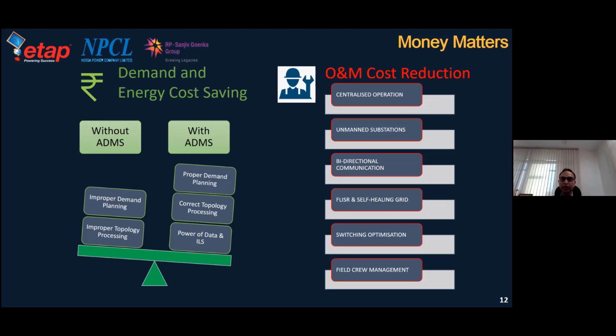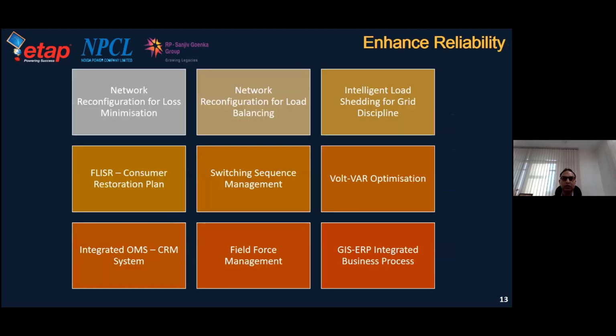In the fault localization, isolation, supply restoration scheme, one has to do the switching on the system so that faulty sections can be isolated, and through alternate sources, supply to the entire consumer base can be restored. But in the self-healing grid, there is no requirement of any human intervention. Field crew management and switching optimization have all really helped to reduce the cost. For example, with field crew, otherwise we might have had to increase the field manpower, but through optimization, with real-time data related to the field crew available, we were able to do the cost reduction. So this has really translated into an overall enhancement in reliability.